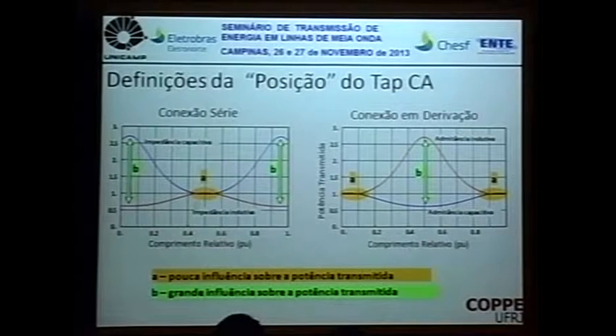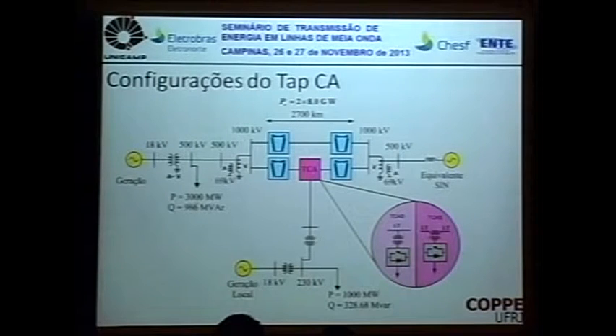The first question was where to position the tap. So we scan the circuit with impedances, where I can identify in this unitary length which are the nodal points, the main points where I need to connect my system. If I want to make a series connection, around the middle of the line would be the most proper place because it works with the minimum of power transmission. But if I want to connect it in shunt, I have the terminals as the most proper points of connection.